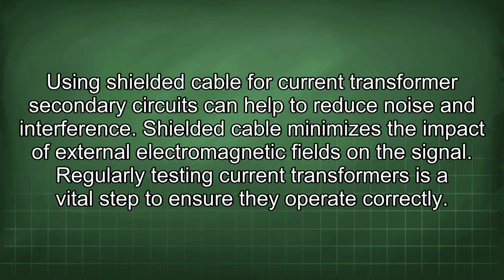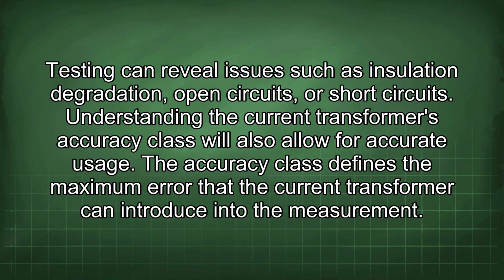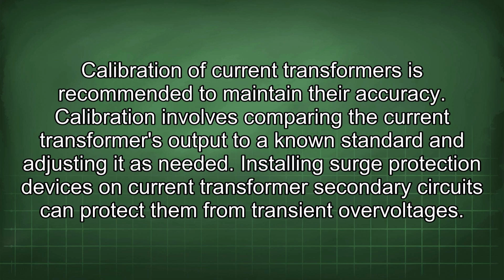Regularly testing current transformers is a vital step to ensure they operate correctly. Testing can reveal issues such as insulation degradation, open circuits, or short circuits. Understanding the current transformer's accuracy class will also allow for accurate usage. The accuracy class defines the maximum error that the current transformer can introduce into the measurement. Calibration of current transformers is recommended to maintain their accuracy.